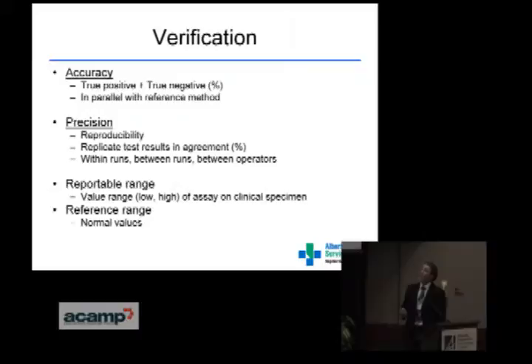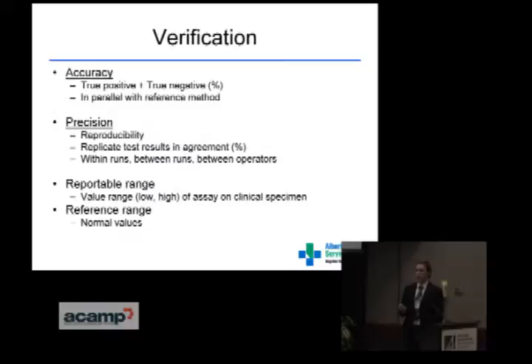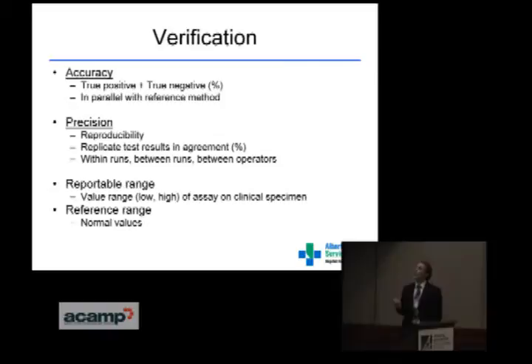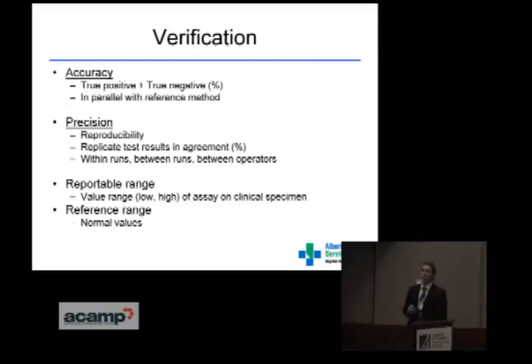The verification is really what I want to draw your attention to, because this is probably very similar to your approach as a manufacturer for how to meet Health Canada and FDA requirements for your medical device application. In my practice, at minimum I have to satisfy accuracy and precision. Accuracy is the rate of true positive and true negative values in any head-to-head comparison of your test method versus your reference standard. Precision — reproducibility — is how confidently the test can reproduce the same result, whether within runs, between runs, or between operators.